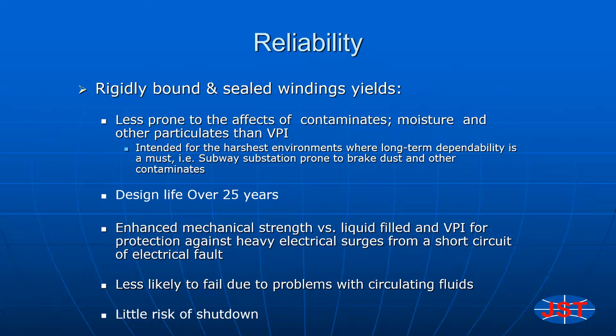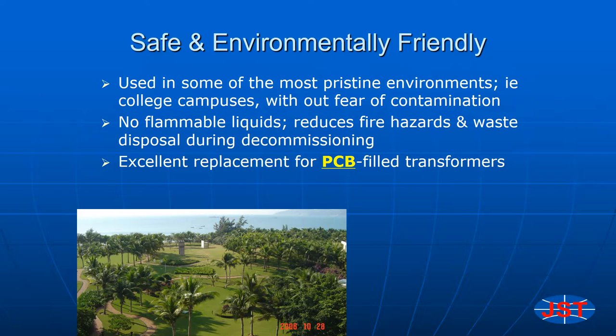When you see that each set of coils is rigidly cast in a solid block of epoxy, it should be easy to understand that this structure is less prone to the effects of contaminants, moisture and other particulates than the transformers with a varnish insulation system. Design life is typically specced to be 25 years, but actual design life is usually well beyond that. Mechanical strength is superior to all other types of transformers and outperforms them with their ability to withstand an electrical fault without damage. Also, cast resin transformers will not encounter problems associated with the restriction of fluids.